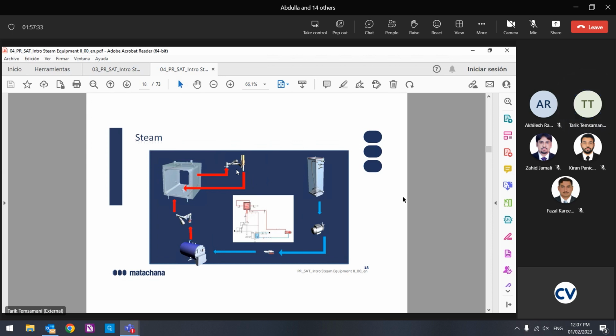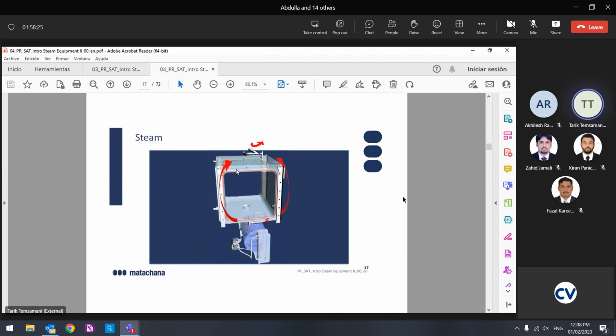Now I ask you. The jacket is smaller, the chamber is big. I have to reach a pressure or heat this chamber. Is the steam from the jacket to the chamber enough? What do we do? The steam will go in pulses. I am asking: we get steam from the jacket to the chamber, and I want to reach, for example, the maximum pressure. This quantity is not enough, but it will go in pulses. The jacket will again take steam from the generator in pulses, so with multiple pulses, it will go to the chamber.